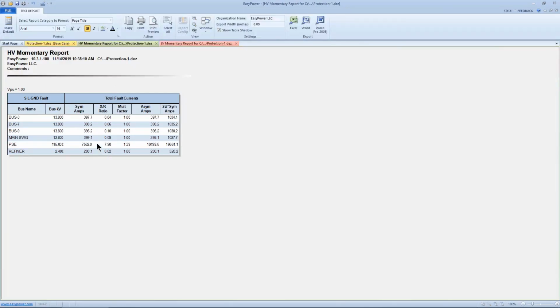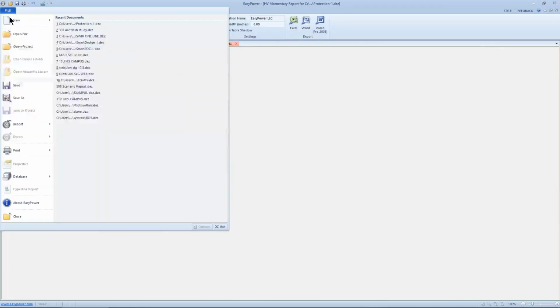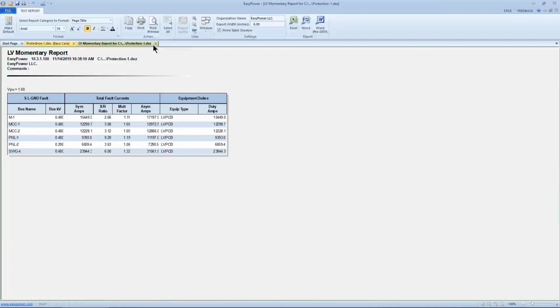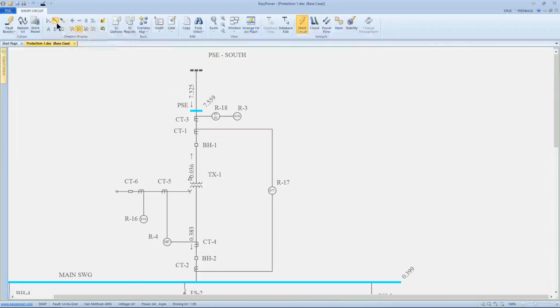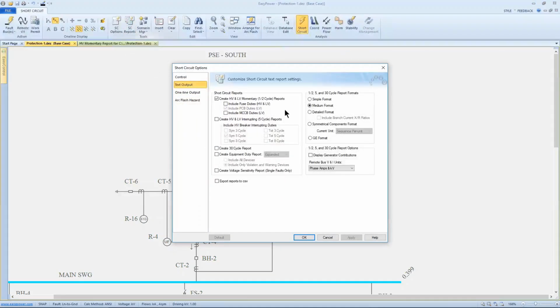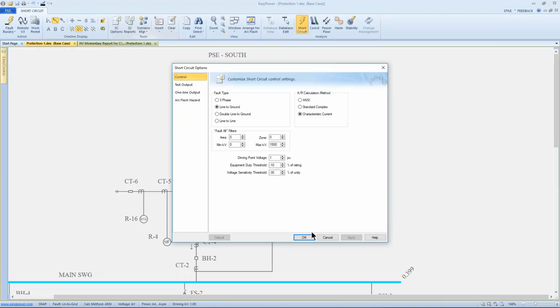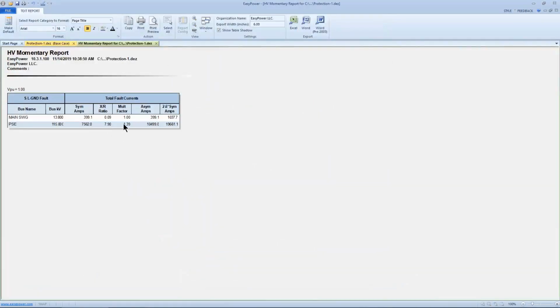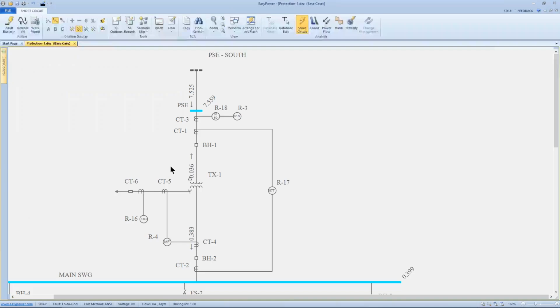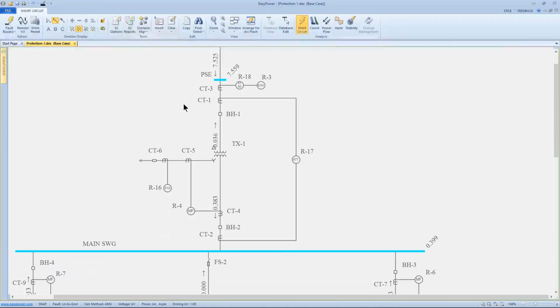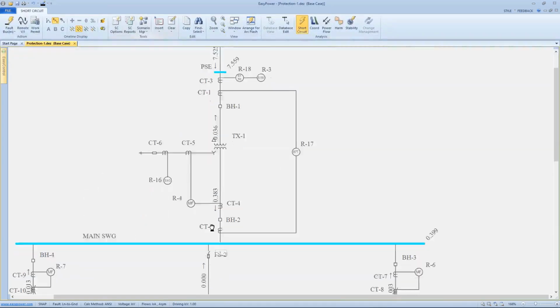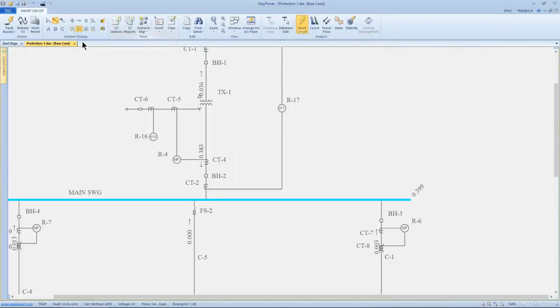Yeah, so we'll get different values. I'm showing PSE rather than just the one. Let me close this and try it again. I want an intermediate current. I want to fault the buses. I want to look at my short circuit reports, and this is in the characteristic. Let's see if I got this right. Still getting 7.9. I've got to check my notes on that one. Point being, the X over R will be recalculated based upon the different method used, and it's that value that can impact the symmetric fault current contribution during a fault.